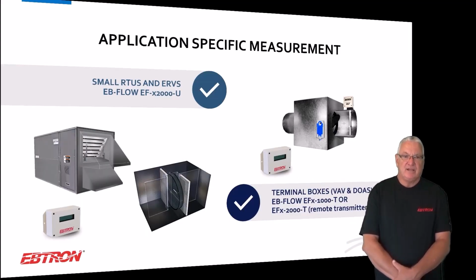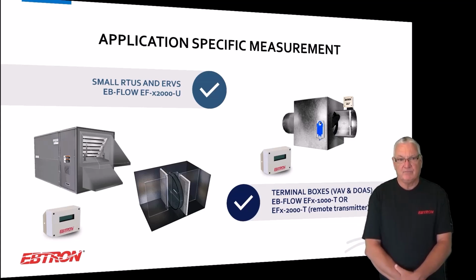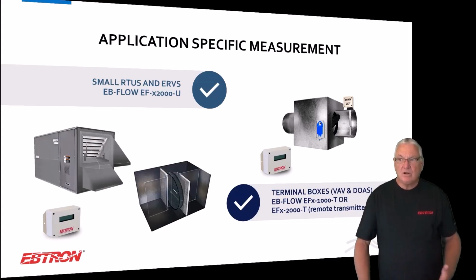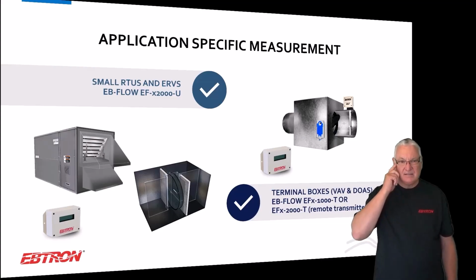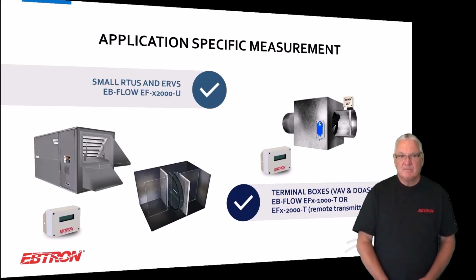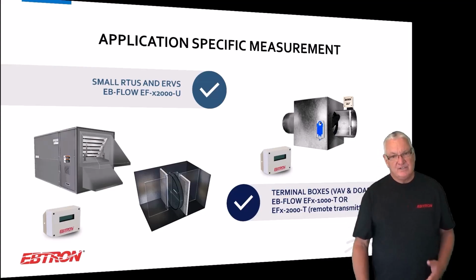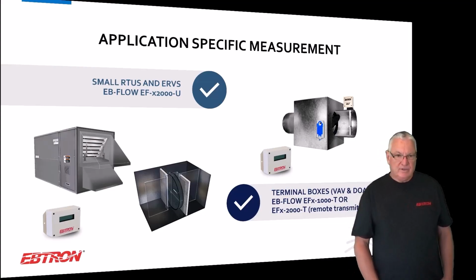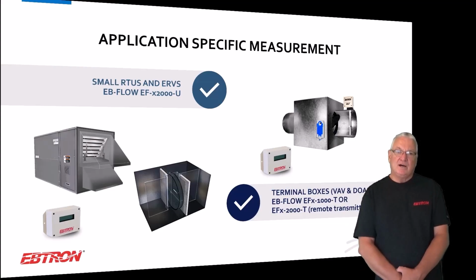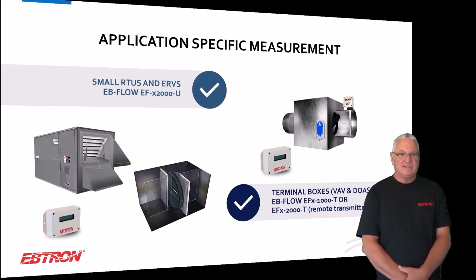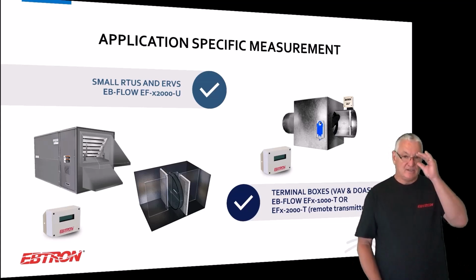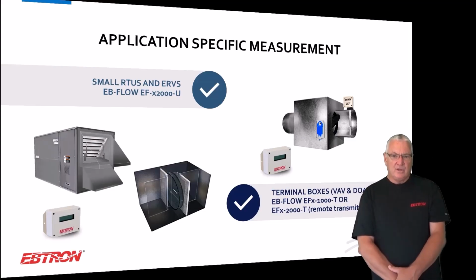Application-specific measurement, so when you get into smaller RTUs, maybe the EBTRON Gold or Hybrid isn't the right solution, so we have a product for that small. I'd say ideally 6 ton, 10 tons maybe pushing it, but 5, 6 ton units. You have these rooftop units on schools. You should really measure the outside air on them. You have some desiccant wheel energy recovery units that I think this is perfect for. You can get the airflow of each side of the wheel with a single device. Okay, you just set the transmitter up to output both.